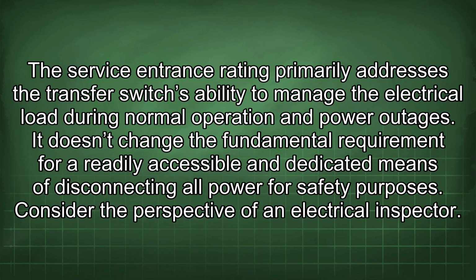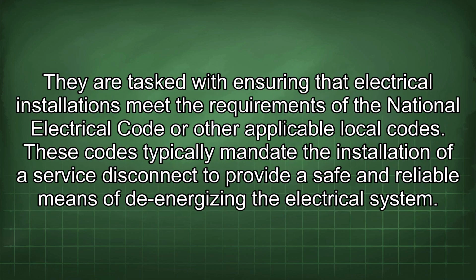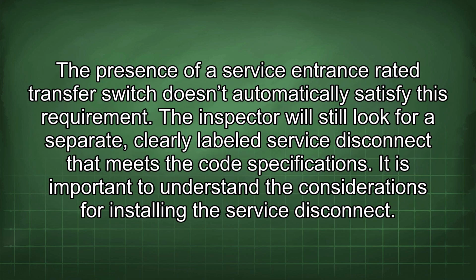Consider the perspective of an electrical inspector. They are tasked with ensuring that electrical installations meet the requirements of the National Electrical Code or other applicable local codes. These codes typically mandate the installation of a service disconnect to provide a safe and reliable means of de-energizing the electrical system. The presence of a service entrance rated transfer switch doesn't automatically satisfy this requirement. The inspector will still look for a separate, clearly labeled service disconnect that meets the code specifications.